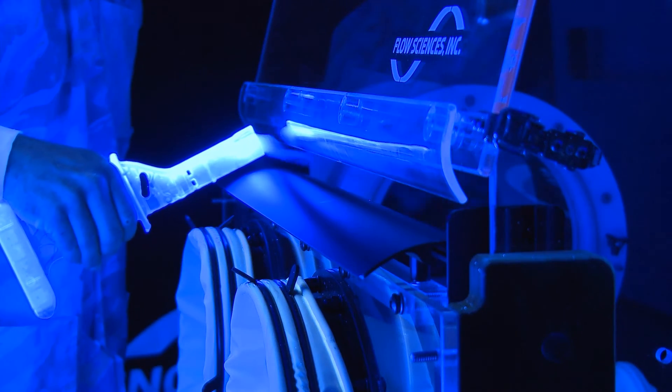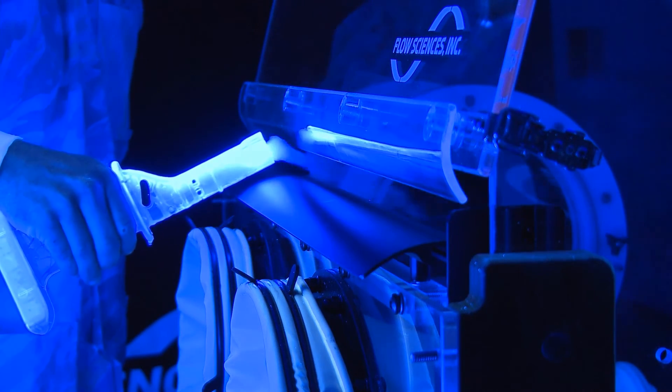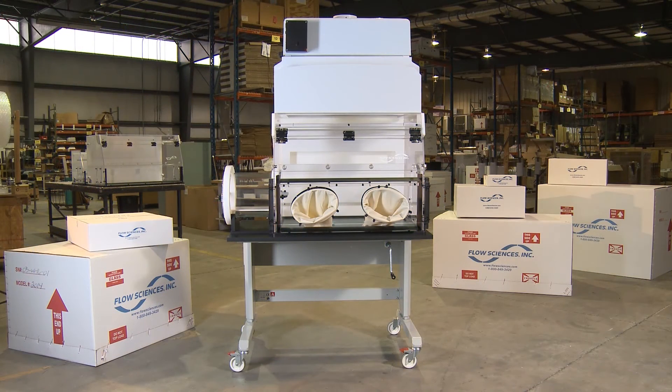As air enters the hybrid isolator, air foils help eliminate turbulence and ensure a smooth air flow, while plenums direct the proper flow of air internally. HEPA filtration, with bag-in, bag-out filter removal, keeps the work environment safe and contaminant free.